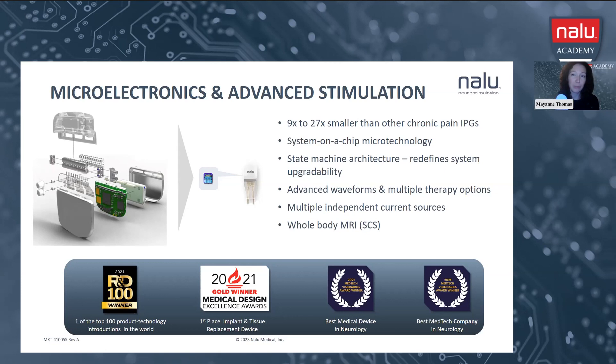The therapy disk can also serve as a rudimentary remote. The other 20% of the system — the green computer board — is the smarts of the battery IPG. Our engineers micro-sized that technology into a chip, then encased these smart electronics — our true fully-fledged IPG — into a ceramic molding and then hermetically sealed the device. What this means to you and your patient is that without that battery component being embedded with the IPG, there's nothing inside the system that will degrade over time.